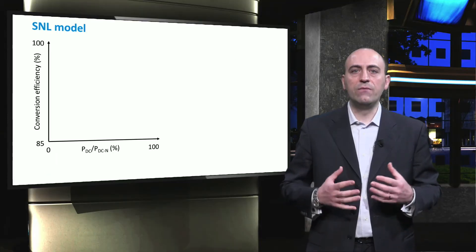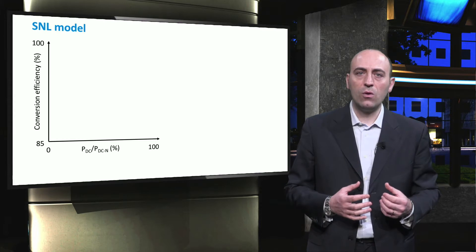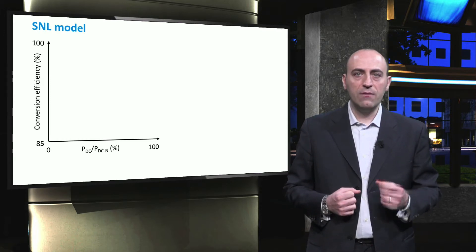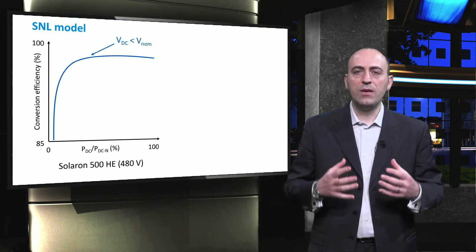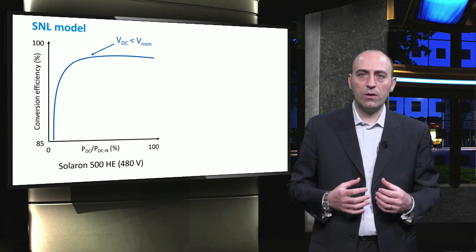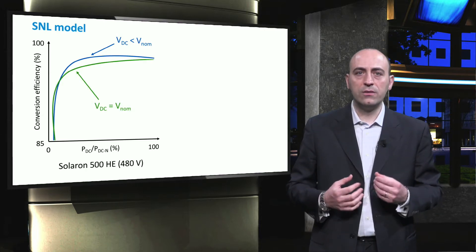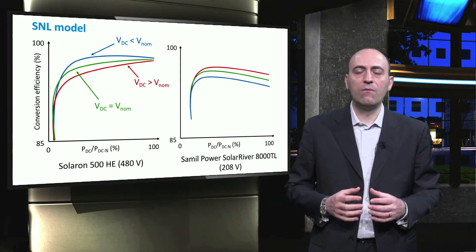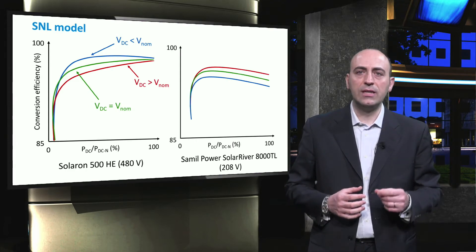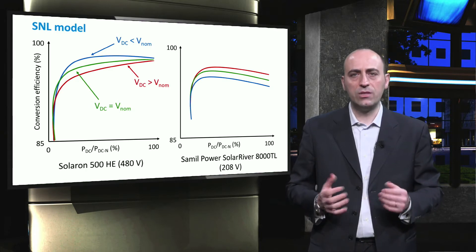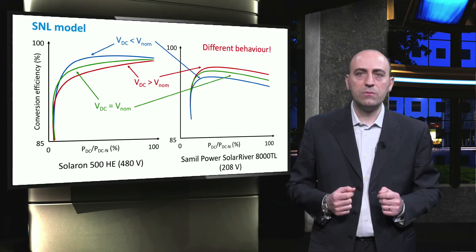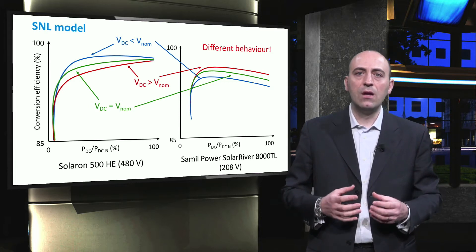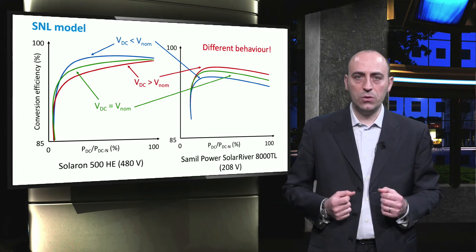The dependency of the inverter efficiency on the DC input voltage is a very complex phenomenon. For a given inverter, there is a different behavior when the DC voltage is lower, equal, or higher than the nominal voltage of the inverter. Nevertheless, for a different type of inverter, a higher voltage can lead to higher efficiencies, or vice versa. The differences between different inverter types can partially be explained by the different types of switches used.